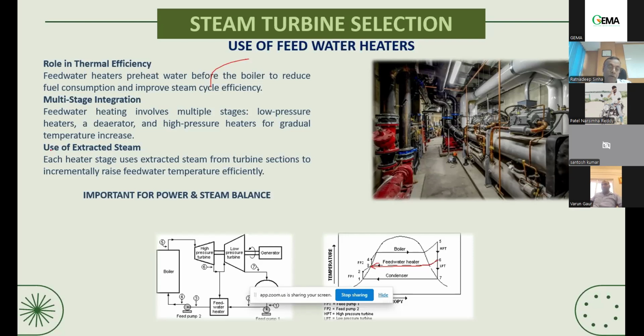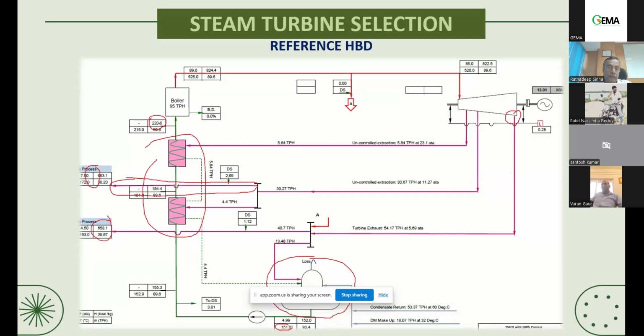boiler fuel consumption. For example, if you put a higher heat to the boiler, suppose this heat I am putting at 220 degrees centigrade, then consider the absorbed heat requirement of the boiler. This is the enthalpy of the main steam, 824, and this is the enthalpy of feed water at 220. So this difference is, say for example, 604. Now if the feed water temperature is coming down to say 120, then obviously my fuel consumption will be higher, but also my boiler will be bigger. So capital cost wise also there will be some saving if I introduce feed water heaters.